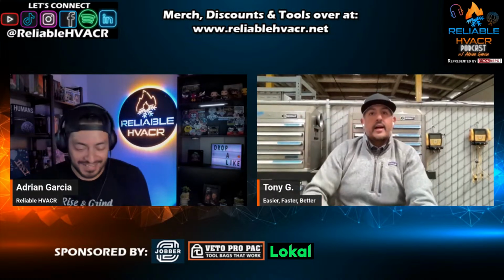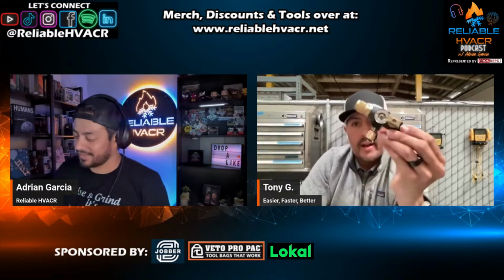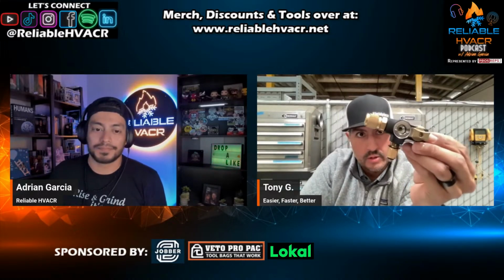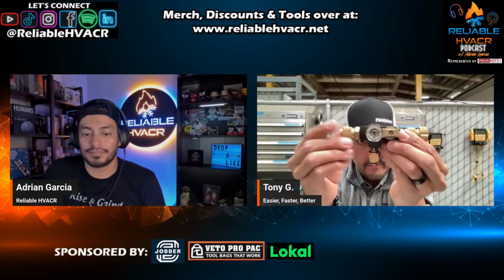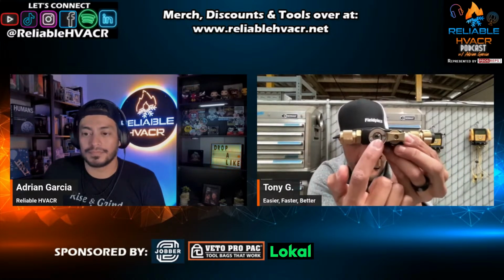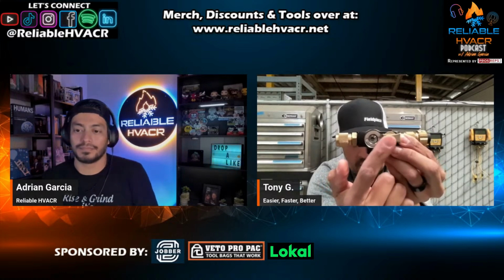Yeah, exactly. So what if we integrated a sight glass into a valve core removal tool, right? And so this is the first innovation that we have with the Fieldpiece valve core removal tools: we've integrated a sight glass that's on the system side of the ball valve.